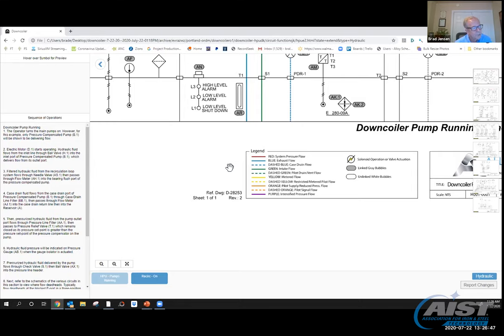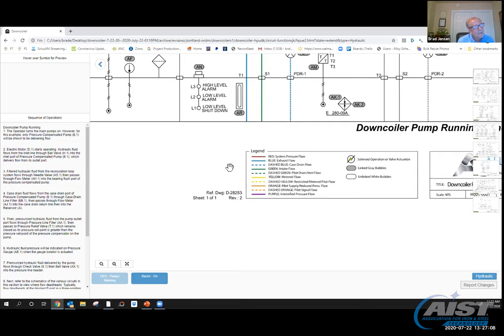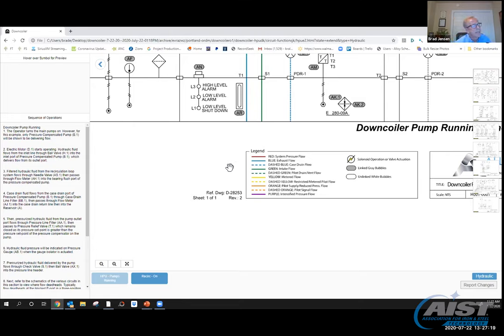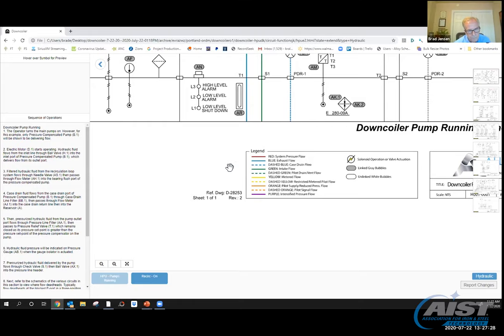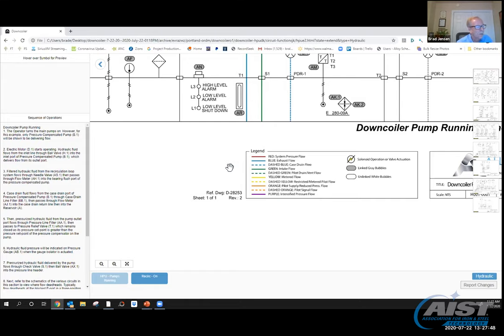I have a legend that is very important for you to understand. This is an ISO international standard colorization of the condition of the fluid or dynamics of the fluid associated with what color it should be. If I'm coloring a specific circuit or related event: red is pressure—red is always pressure. Blue is always exhaust, return flow, tank flow. A dashed blue means it's low pressure tank fluid coming out of a case drain going back to the reservoir. Green—solid green—is suction or intake flow. A dashed green is pilot drain or vent flow. Some valves downstream are pilot operated, meaning an electrical solenoid valve is piloting fluid that powers the valve open or close. It could have internal or external drain.